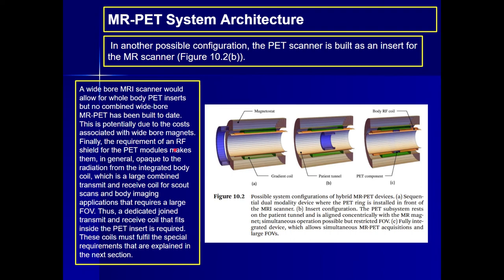Finally, the requirement of an RF shield for the PET modules makes them, in general, opaque to the radiation from the integrated body coil, which is a large combined transmit and receive coil for scout scans and body imaging applications that require a large FOV. Thus, a dedicated joint transmit and receive coil that fits inside the PET insert is required. These coils must fulfill the special requirements that are explained in the next section.